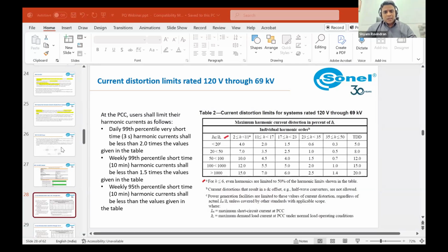A very interesting question. When we talk about renewable power integration, it already has enough issues from a PQ point of view, related to inverter switching and other power quality issues. When they want to connect back to the grid, maybe we'll take that up as a separate session, the relevant standard is not IEEE 519, it's IEEE 2800. You are absolutely right, but from a larger, regulatory perspective, the first step should be to maintain or improve the PQ at the PCC level, then move on to improving the broader scenario.